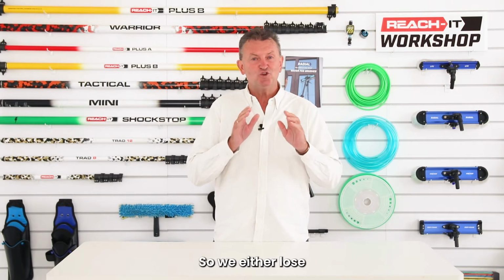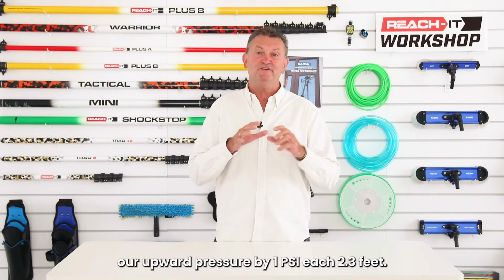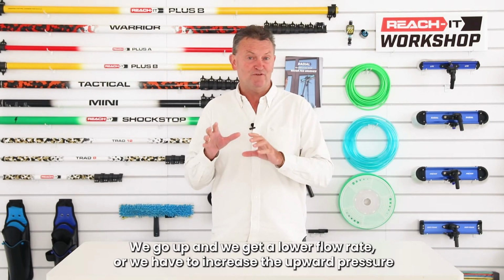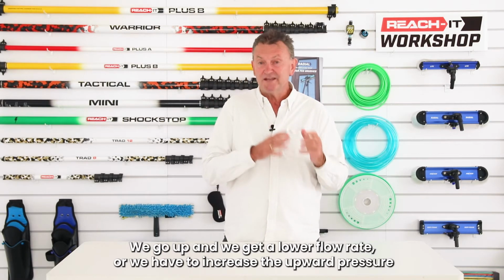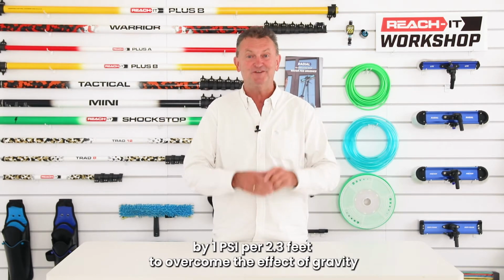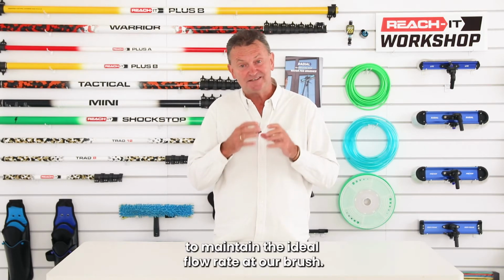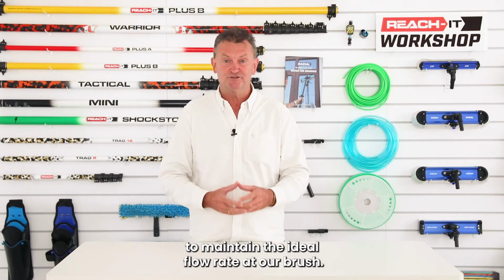So we either lose our upward pressure by 1 psi each 2.3 feet we go up, and we get a lower flow rate, or we have to increase the upward pressure by 1 psi per 2.3 feet to overcome the effect of gravity to maintain the ideal flow rate at our brush.